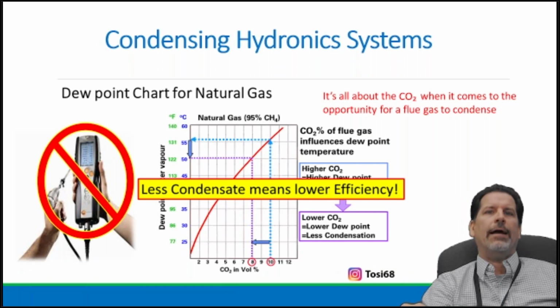Annual inspection, annual maintenance, always get your analyzers on there to confirm. That I can just look, visual stuff is gone. It's no longer acceptable. I can see the color, I see the form, I can see the length. I'm talking about flame here. Get your combustion analyzers on there. This is a life safety portion of what we do.